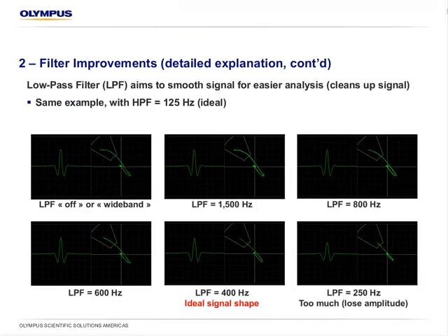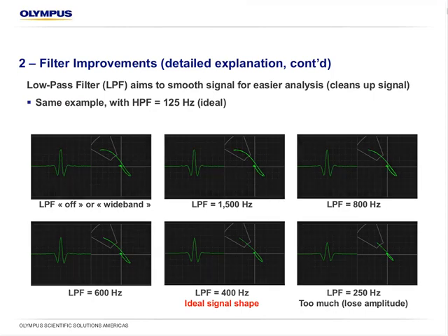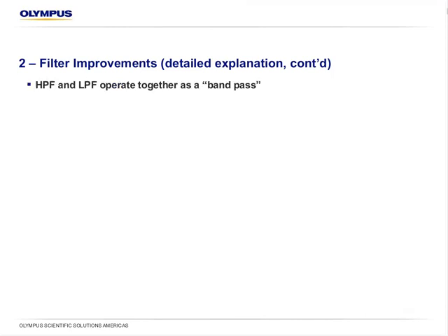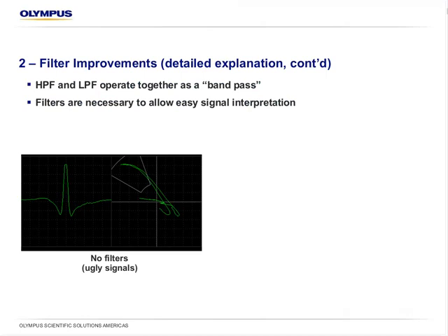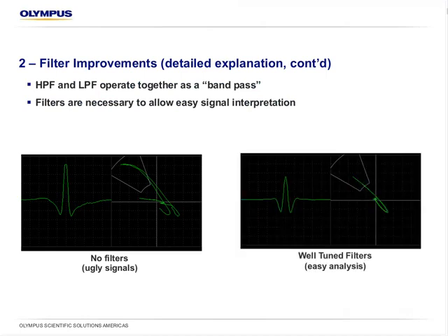So the sweet, oops, I'm sorry, I touched it anyway. The sweet spot would be the 400 hertz low pass here, because we get the best signal without starting to lose amplitude. Okay, so the high-pass filter and low-pass filter operate together as a bandpass. The filters are quite necessary to allow easy signal interpretation. If we compare the original screenshot, no filters, to high and low pass filters being properly adjusted, there's quite a bit of difference, and it's quite a lot easier to see the signal than it is without any filtering.